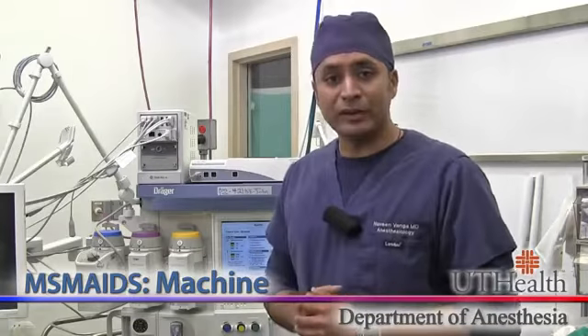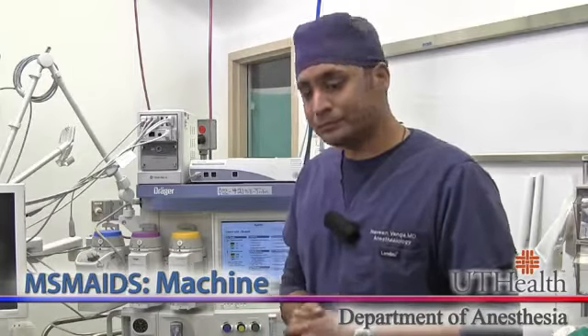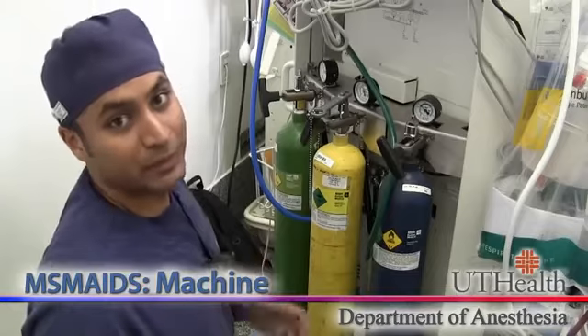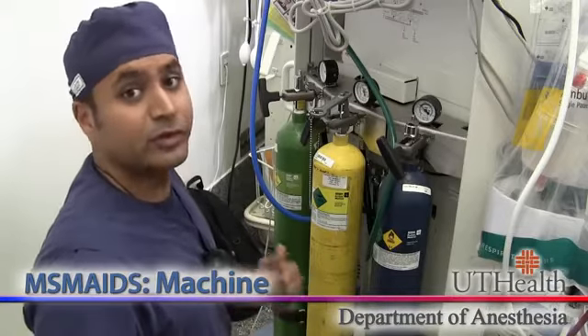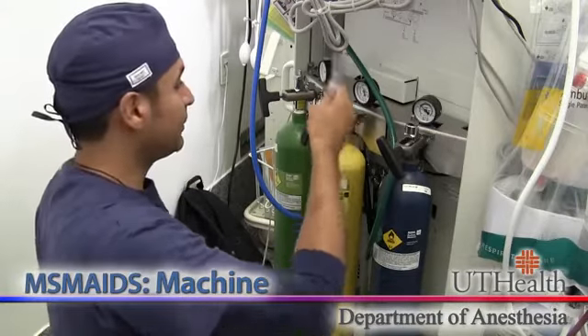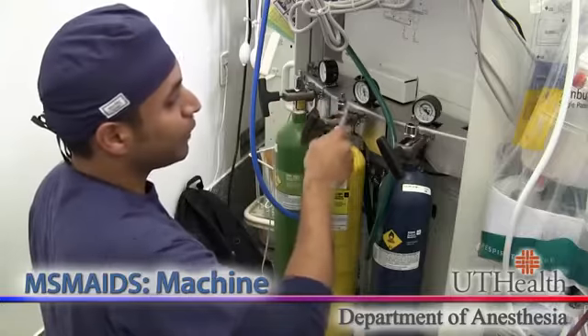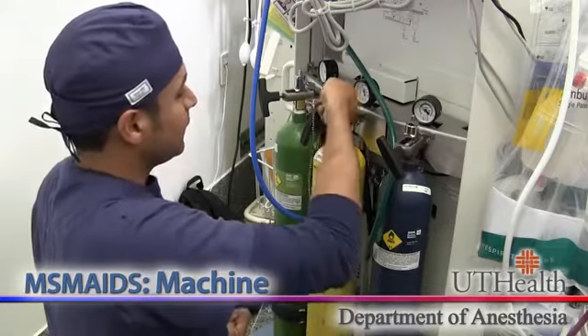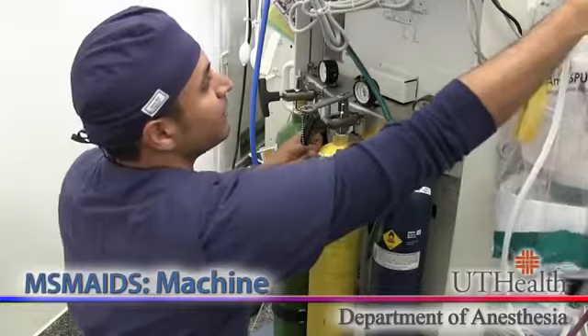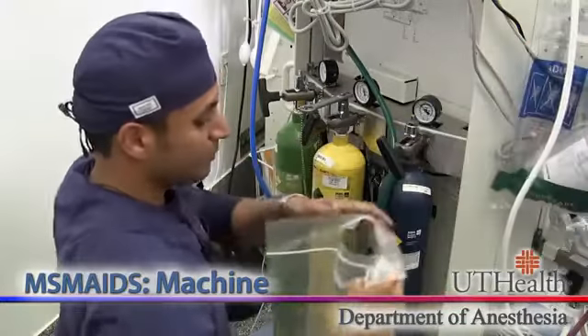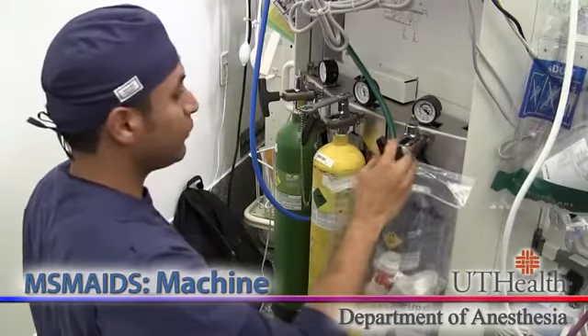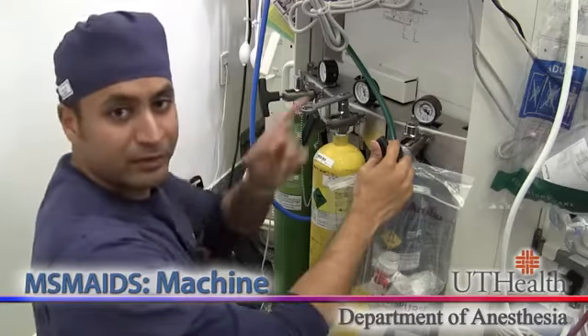Now that we've checked the vaporizers, let's go to the back of the machine to check the E-cylinders. Here we are at the back of the machine. It's important to make sure that you have a wrench and that each cylinder is adequately filled. At our institution, we keep the ambu bags at the back of the machine also, so it's important to make sure you have one of these just in case you need one. Okay, let's go back to the front of the machine.